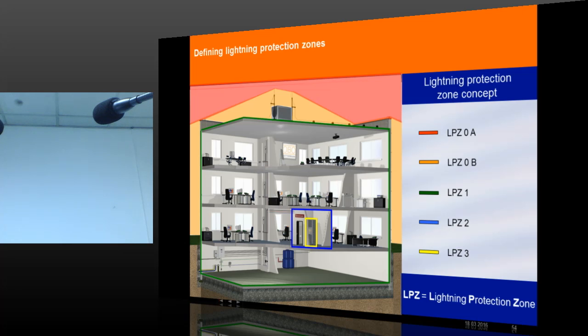You see this area, LPZ 0A. LPZ 0A is an area outside the building where a direct lightning can strike this red area. A direct lightning can strike in this particular place. So 0B, direct lightning will not strike. For example, this side of the building, direct lightning will not strike on that area. Instead, it will strike the parapet or it will strike the air terminal. But this is also a dangerous place because partial lightning current will flow through the area. If you have a down conductor, lightning current is going to flow through the down conductor, which is not allowed inside. It is outside the building.